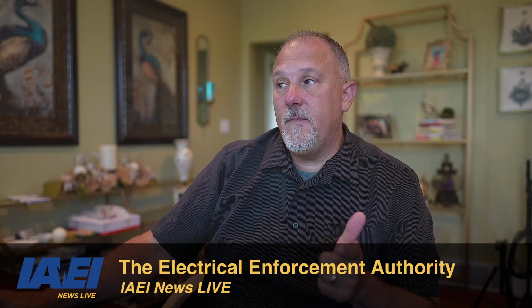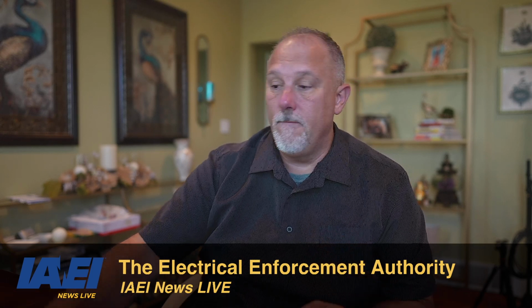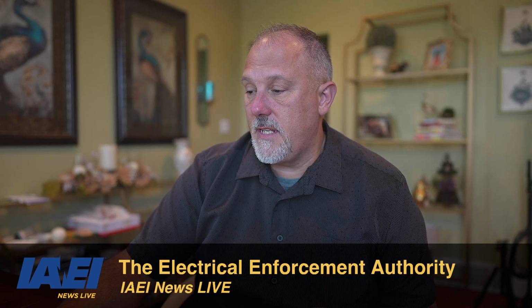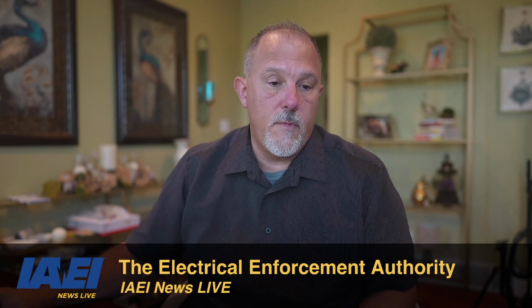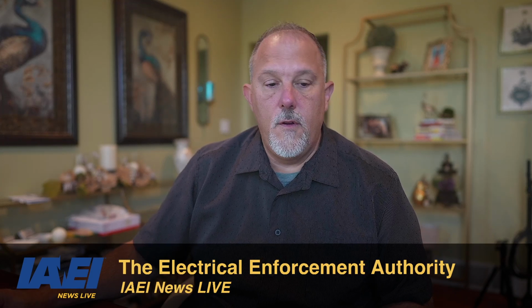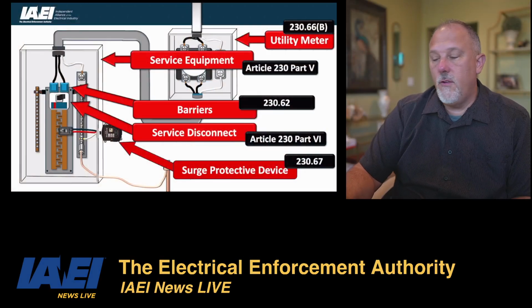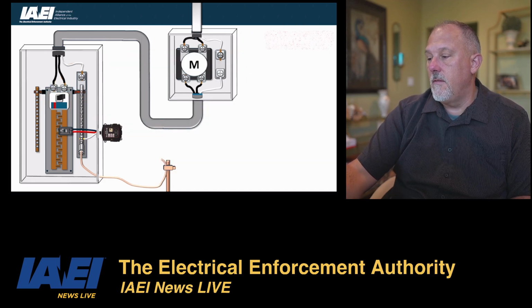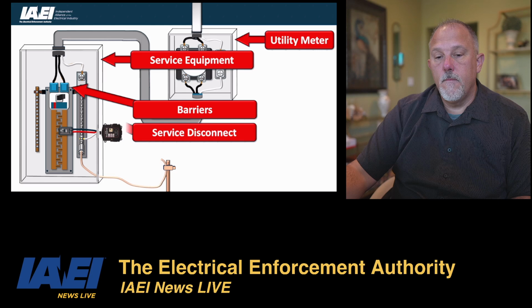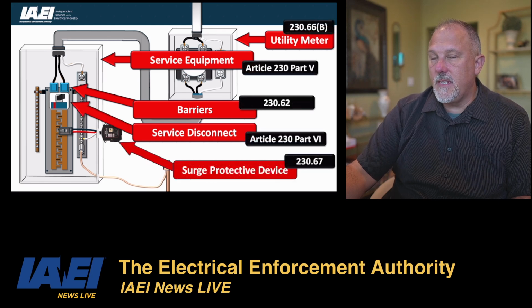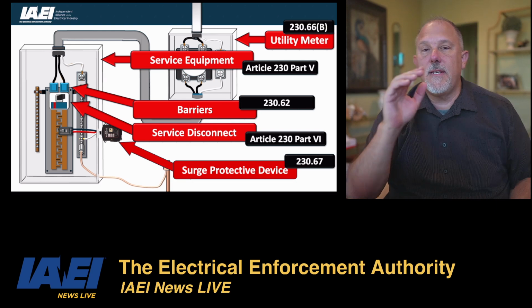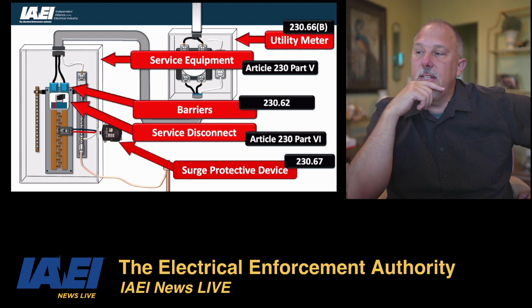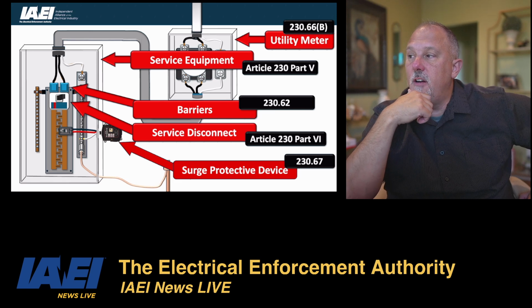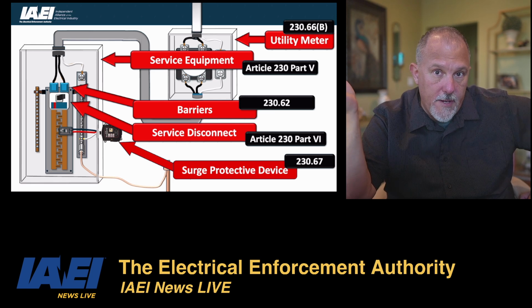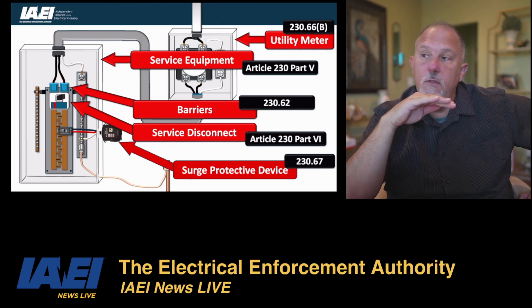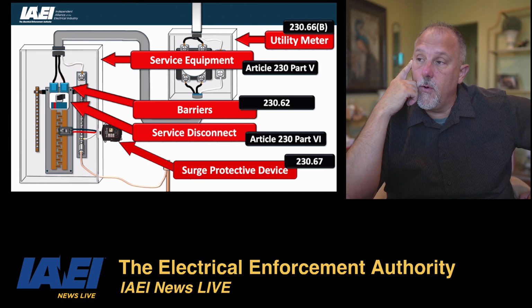Another change that I believe makes sense is in 230.66. Let's take a look at 230.66 for the utility meter. I have 230.66(B) as one of the sections. 230.66 is titled Marking, and (B) is Meter Sockets. It says meter sockets shall not be considered service equipment, but shall be listed and rated for the voltage and current rating of the service. There's no marking requirement in (B). So I am proposing moving that language over to Chapter 4, specifically in 408.